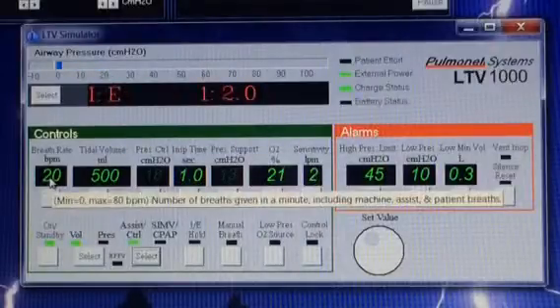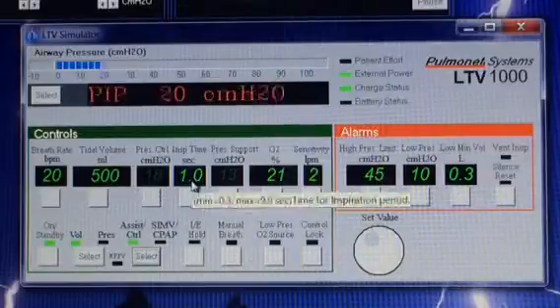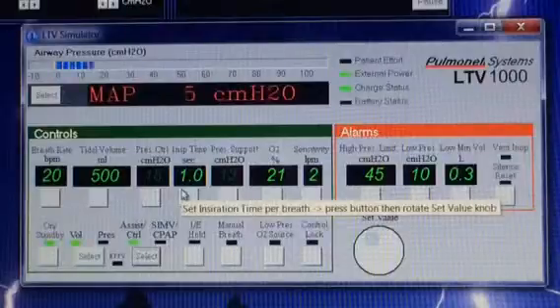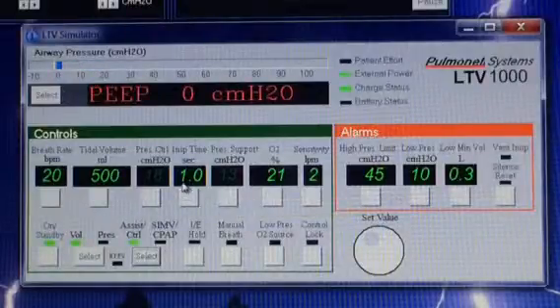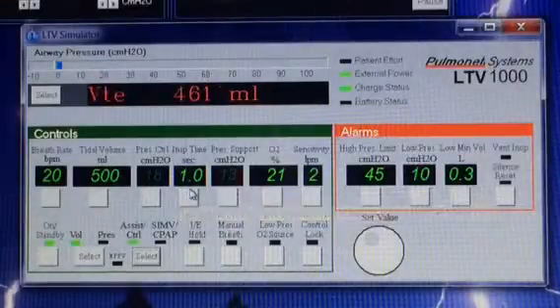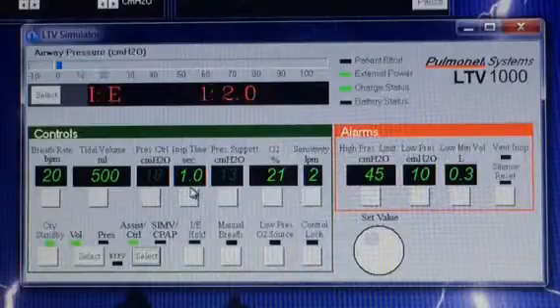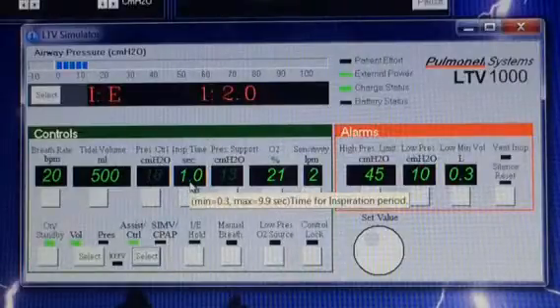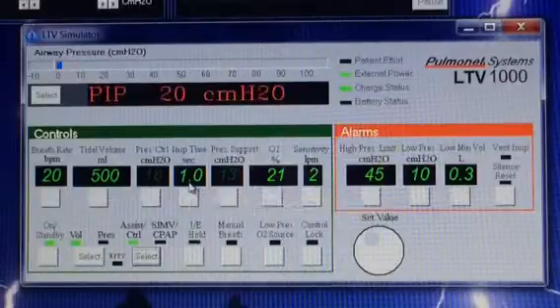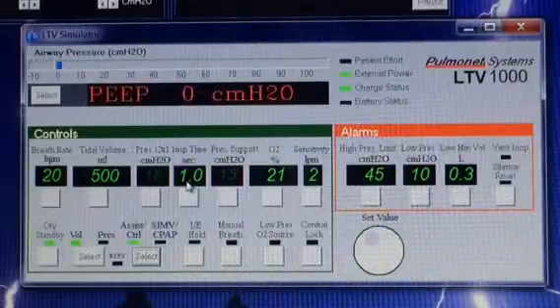So it's giving 20 breaths per minute, and each breath is 500 milliliters. The inspiratory time in this case is one second — that's how much time it's going to deliver that breath over. We can give the breath really fast or nice and slow, and it usually depends on how old the patient is. A neonate usually breathes really fast, so it's 0.4 seconds. A toddler to a tween, maybe 0.6 or 0.8. A teenager to an adult, one second or more — one second is pretty common.